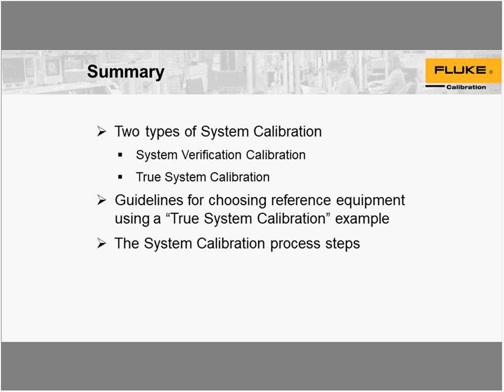Are there temperature sources that go to cryogenic temperatures? We've got the 9190, which is a cryogenic dry well. It goes to -90, and it's fairly stable. Apart from that, the coldest temperature that we get in our standard dry wells or metrology wells is -38 degrees.